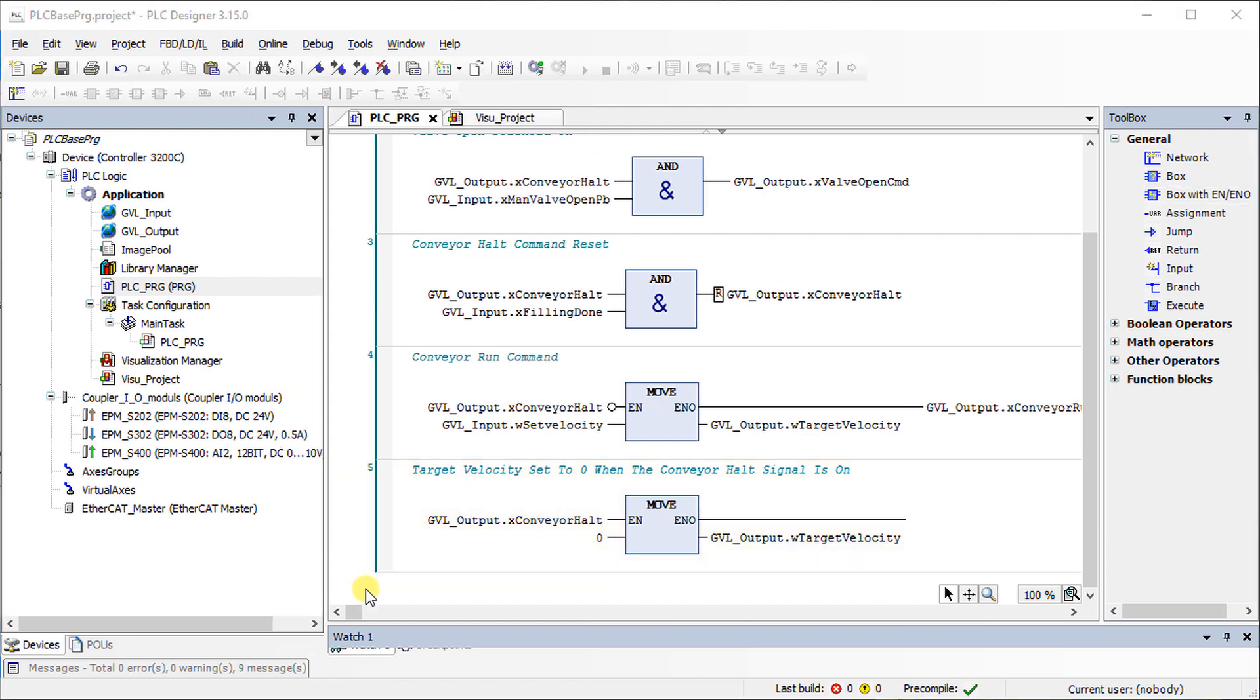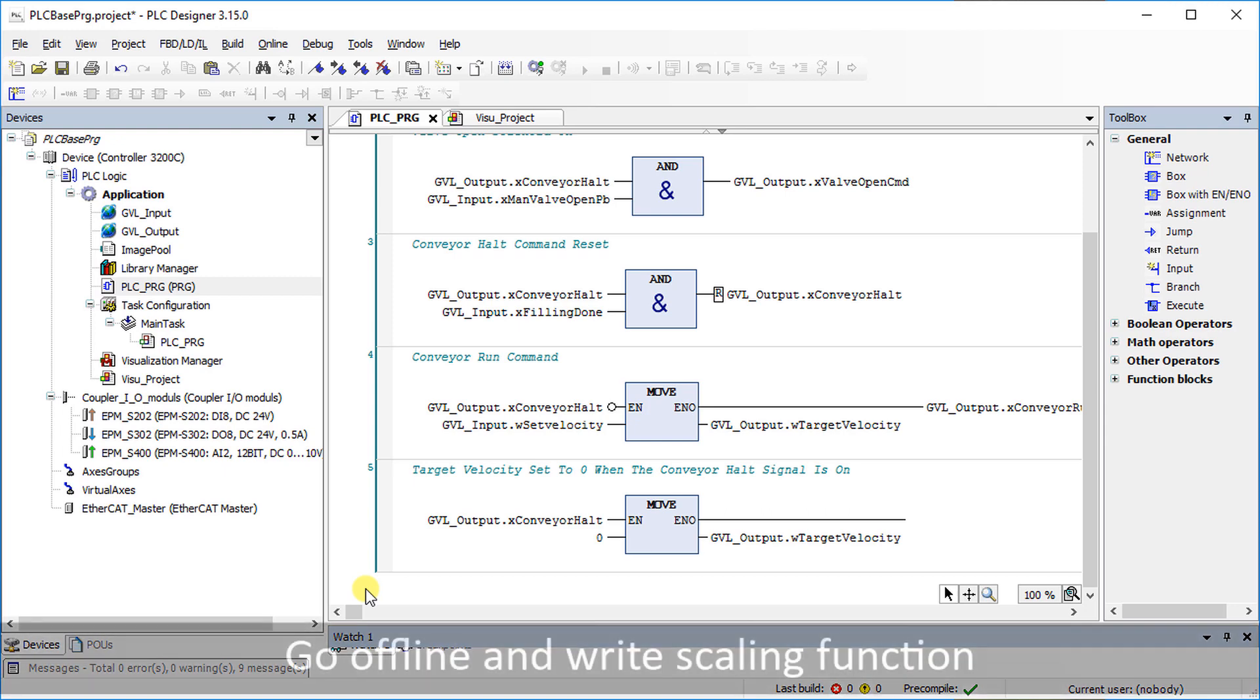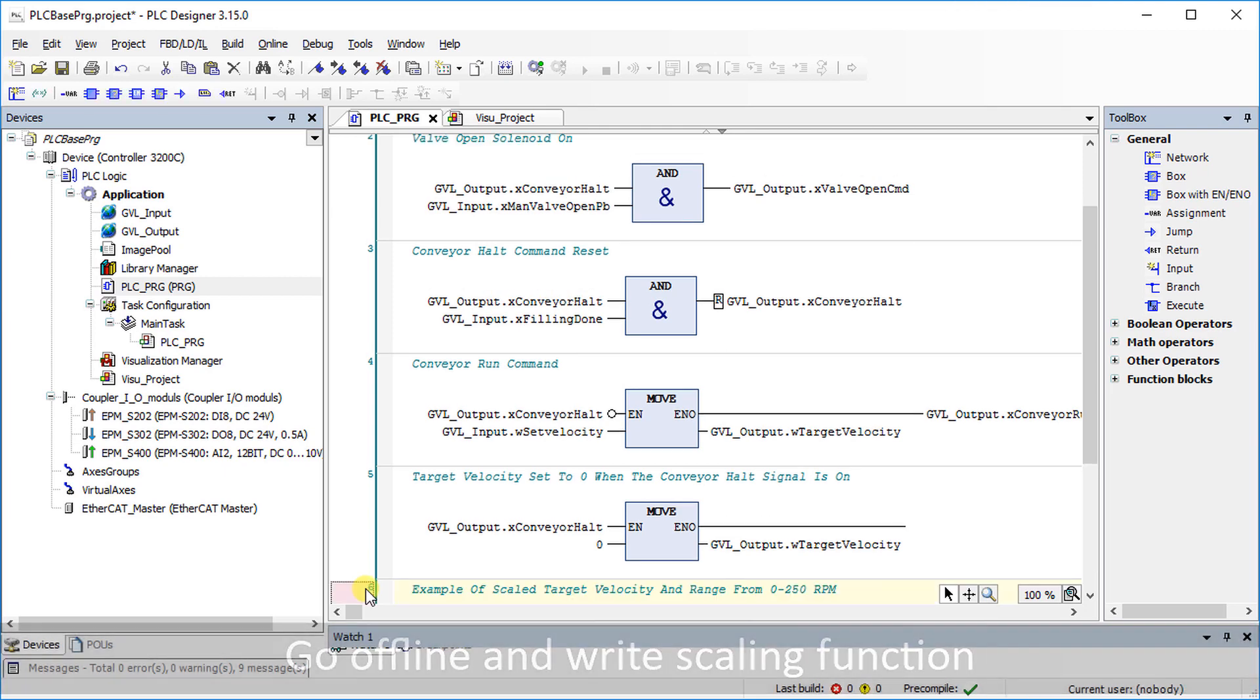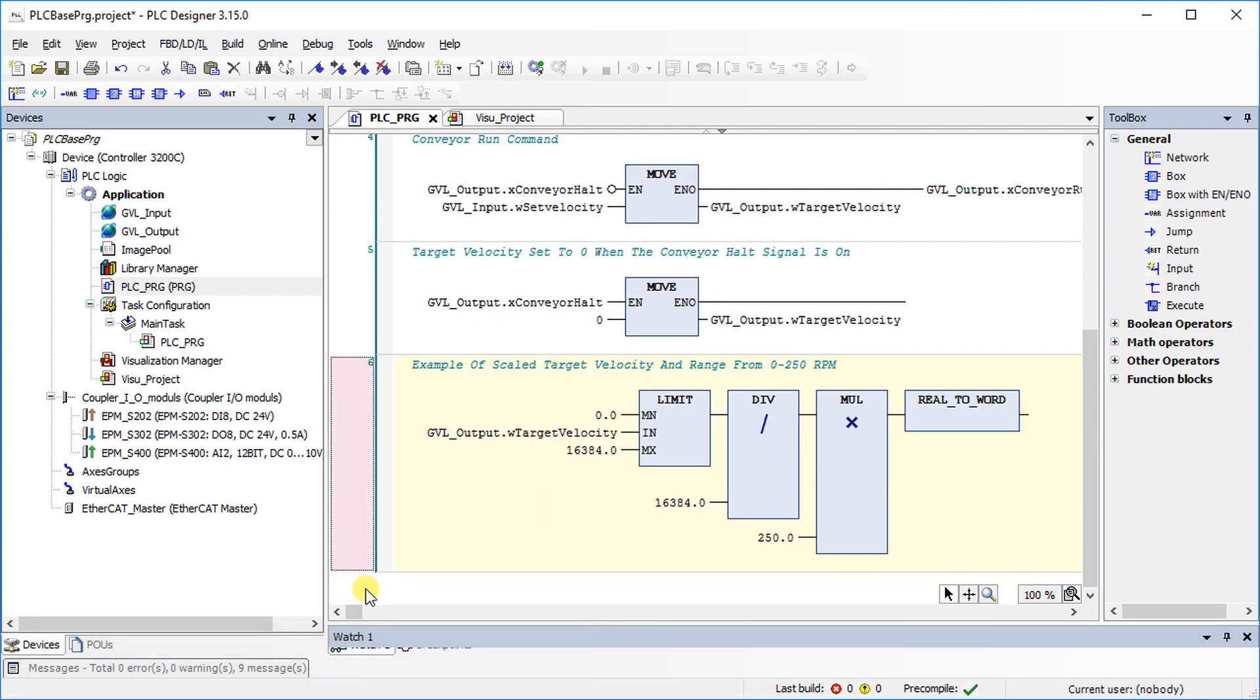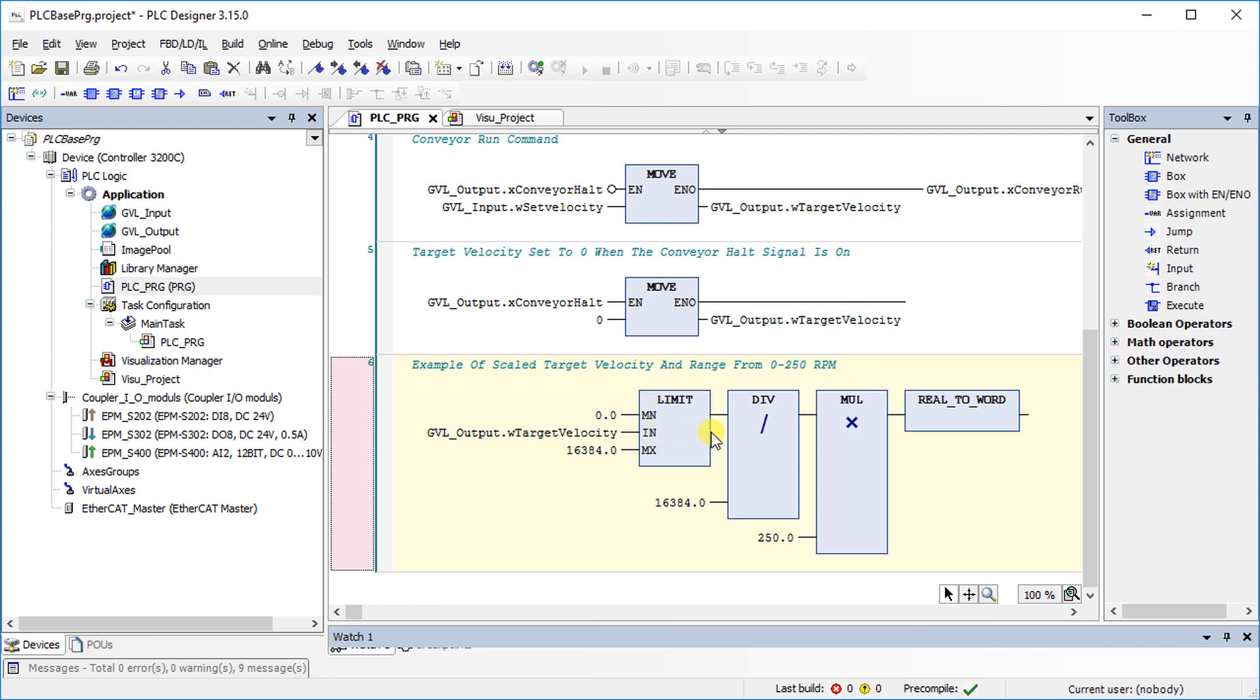Scaling functions are used to scale an analog signal. The example has demonstrated how to write a scaling function. The target velocity is on a scale between 0 and 250 rpm. The limit function defines the analog input's minimum and maximum limit. It is divided by its resolution and multiplied by the maximum scaled value.